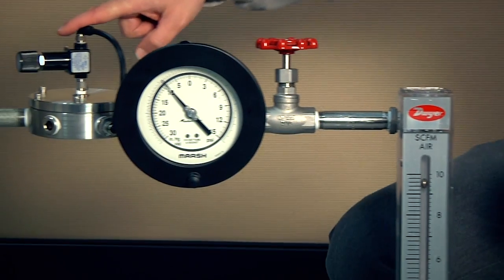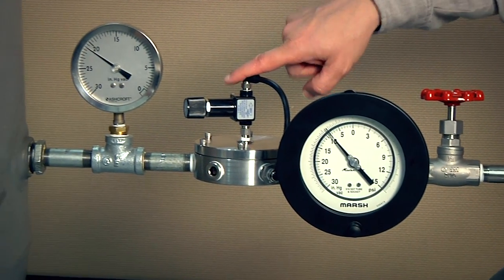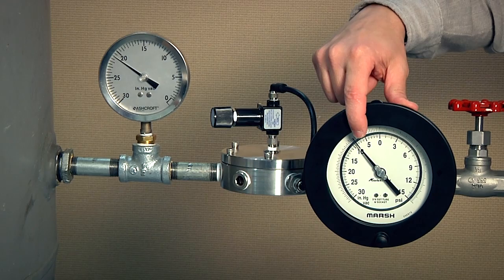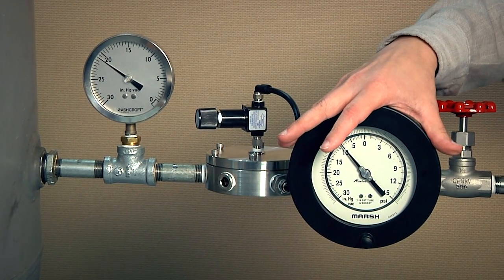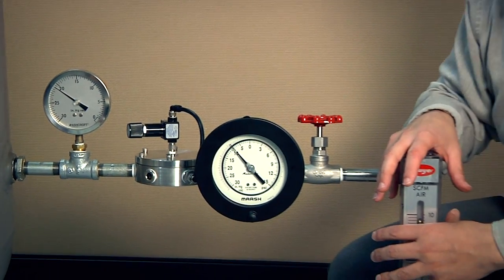Yet if we come back over to the Equilibar vacuum regulator, we'll see that we're still at our 10 inch of mercury vacuum set point. So the vacuum pressure is independent of system flow.